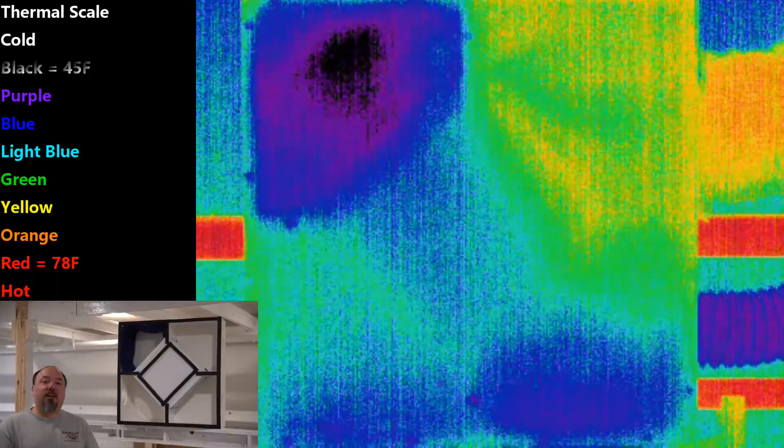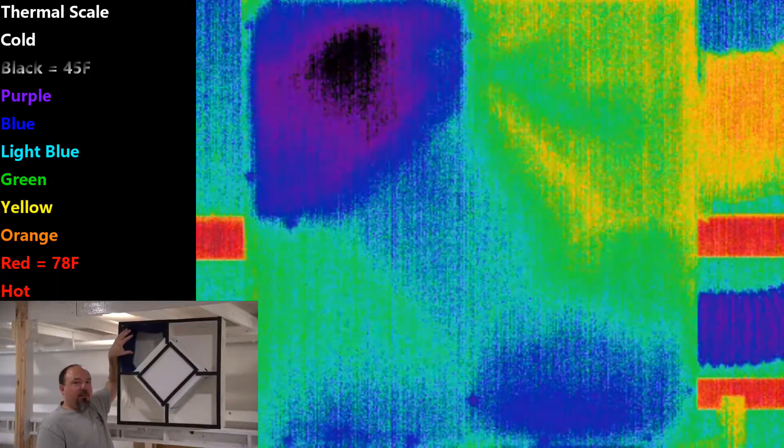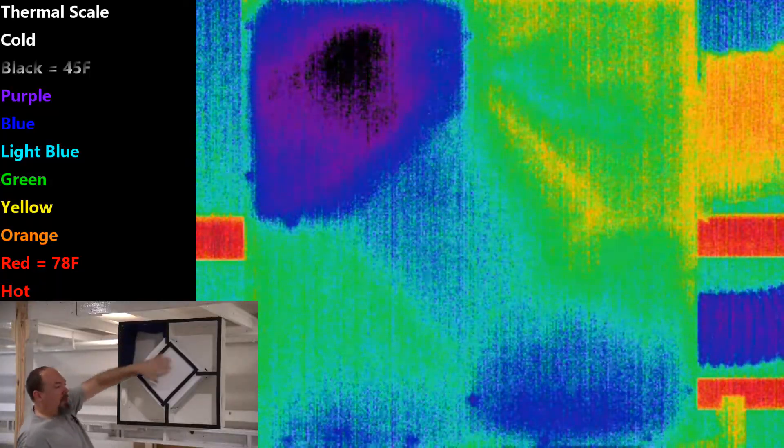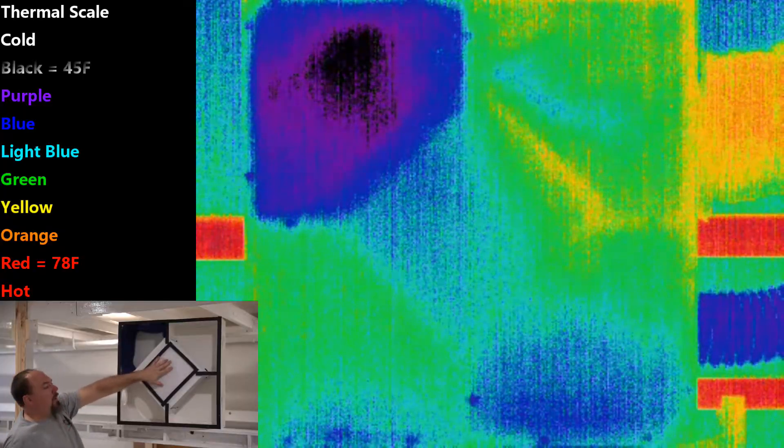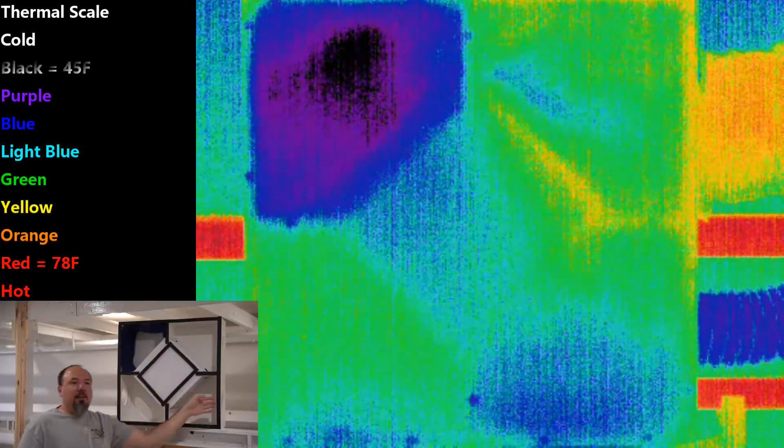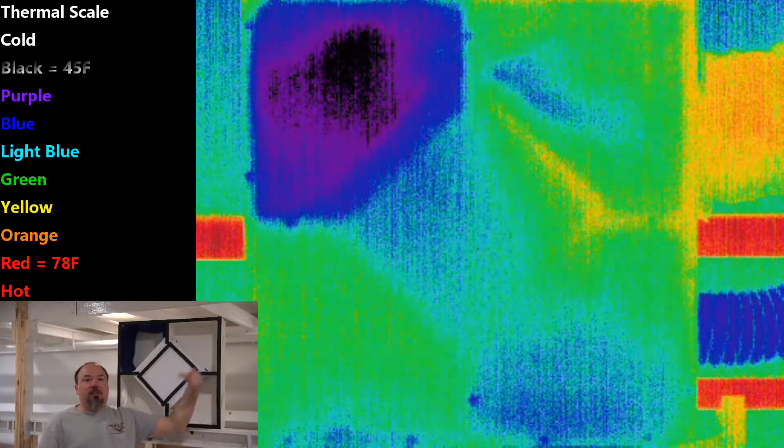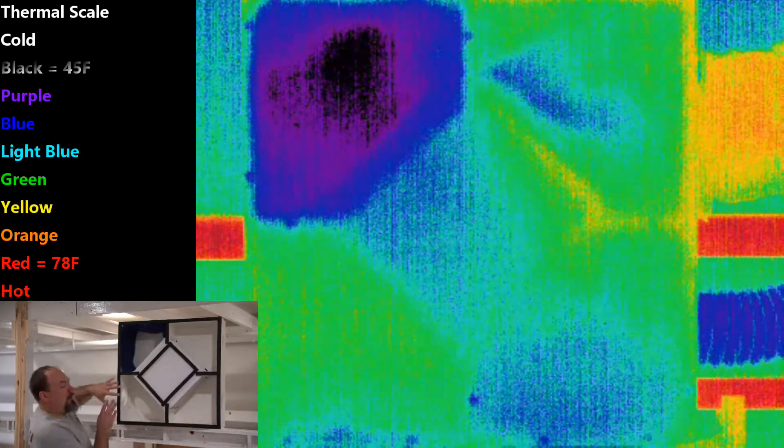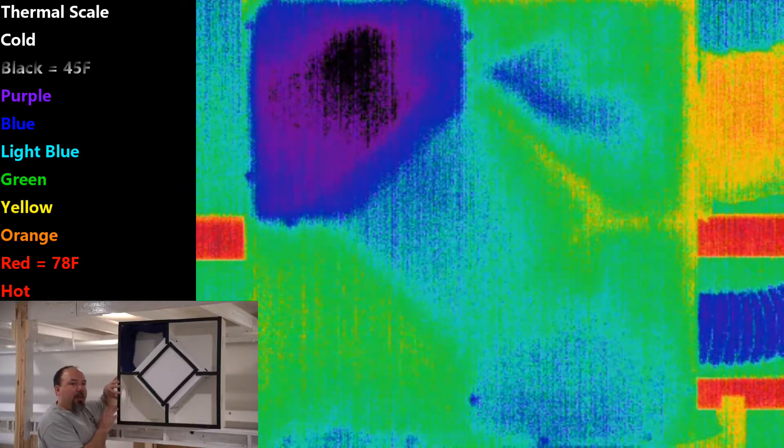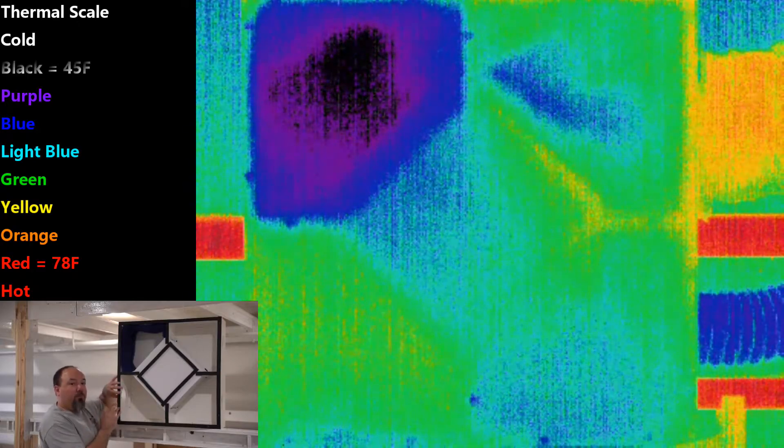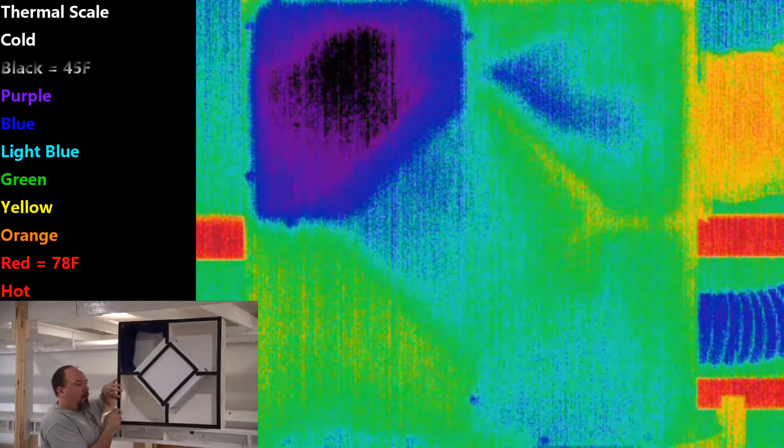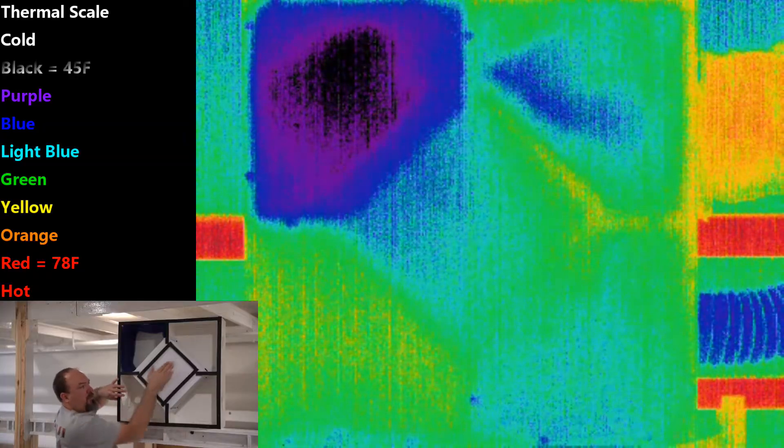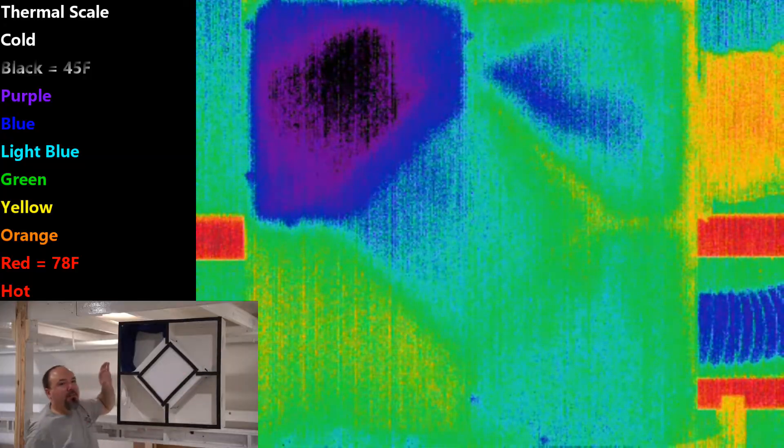So on the top left, you have outside air coming in, which gets passed through the center here, which is the core. And then it goes out and into the fish room through a duct and an inline fan. On the other side here, on the lower right, we have air getting pulled in from the fish room itself. So it's warmer air. It passes through the core in this direction, and it comes out up on the top right. And then that duct gets exhausted outside.